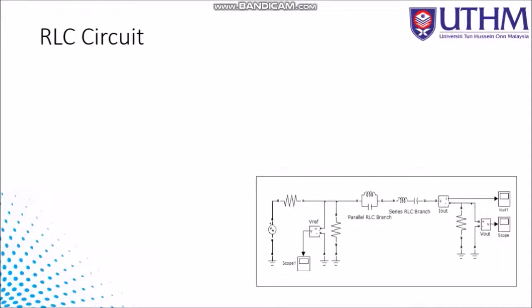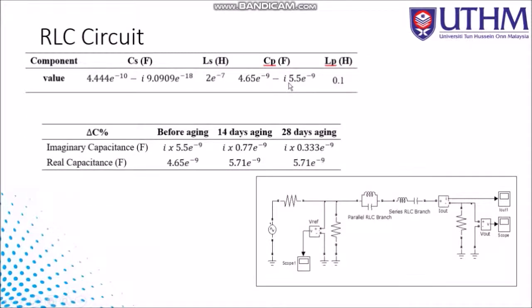This is a basic RLC circuit to represent the transformer as an RLC in parallel and in series. As shown in the table, this is the setup to represent the actual frequency response. We see that imaginary and real capacitance will change when the aging process occurs. Before aging, this is the setup. After 14 days of aging and after 28 days of aging, when we change the real and imaginary capacitance values, we can represent the actual measurement.